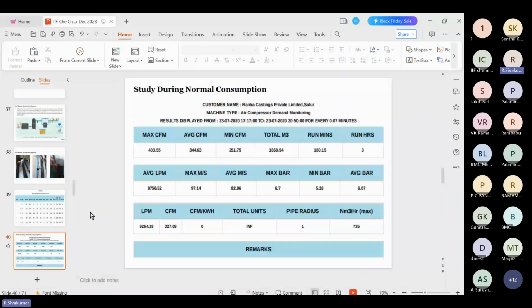Similarly, for one of the foundries, this air study was done during normal operation. It was studied from evening 5:15 up to night 8:50. Every 0.07 minutes, the data was captured. The maximum CFM generated is 403, because there are 2 air compressors running in parallel, each a 100 HP compressor. The average CFM generated from these 2 compressors is 344, and the minimum is 251.